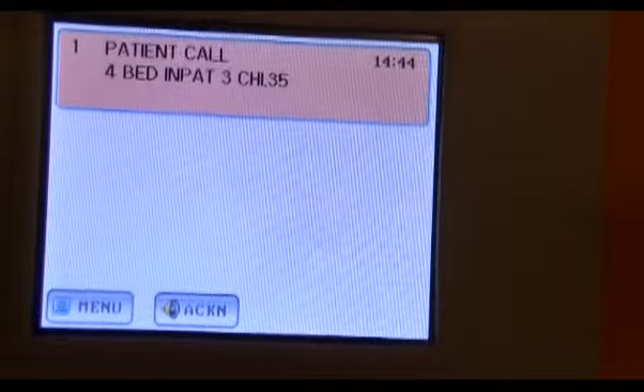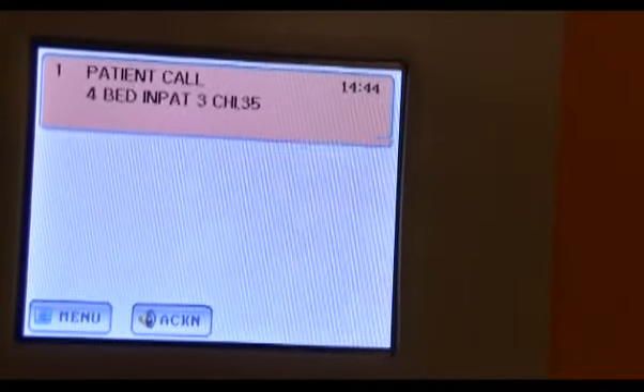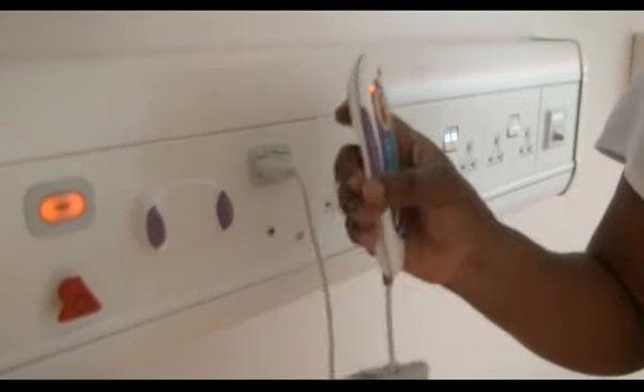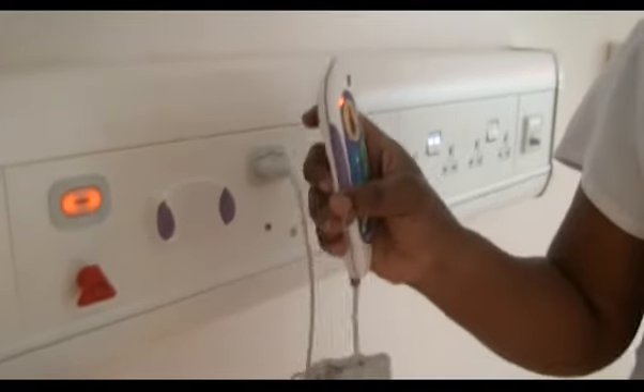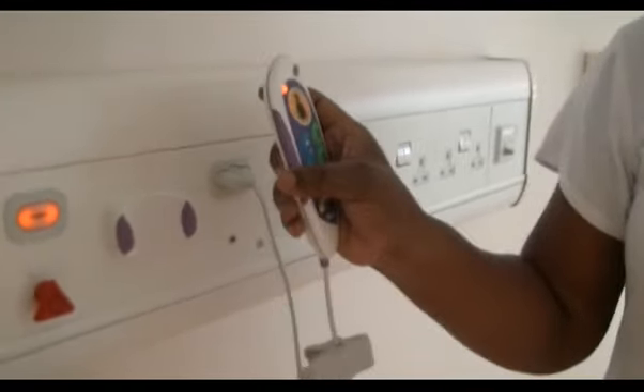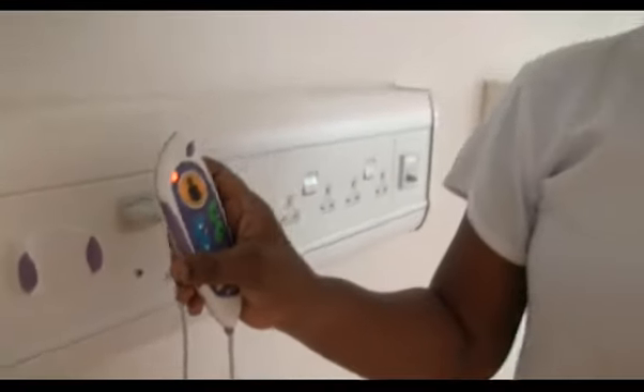When this is pressed, an alarm is set. The nurse, wherever she is, would know that a patient is calling. It is not a continuous alarm, but the sound will be made every 6 seconds and it stops. From the staff base, the nurse will see the room and the bed number, but she cannot reset from the staff base. She must come here to the patient and then reset after she has assisted the patient.